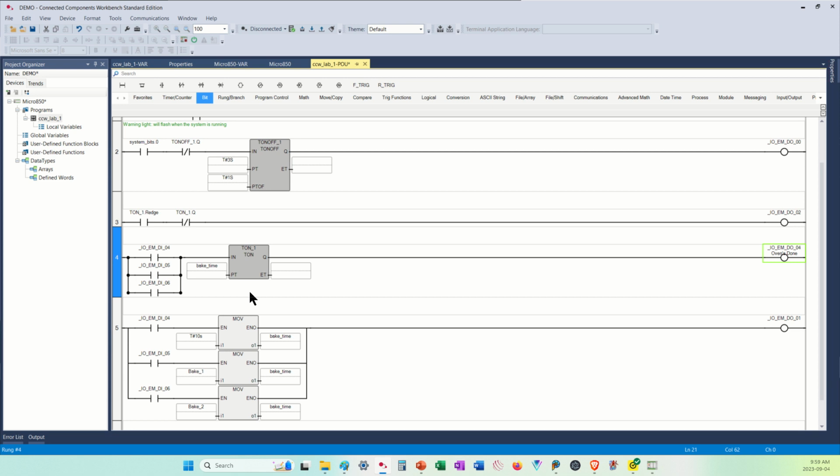I may be turning around at the same time and saying, well, hang on a second, that's going to be impacted by the number of Kaiser rolls or the number of French sticks I'm making, and I might want to adjust my time. I can use product counts to adjust that time. And I would have logic similar to this with the move instructions to actually change the time that I want so that the timing is always perfect and I don't have to sit there and constantly adjust my cooking time. I just have it pre-programmed. When the process changes, my cooking time changes.